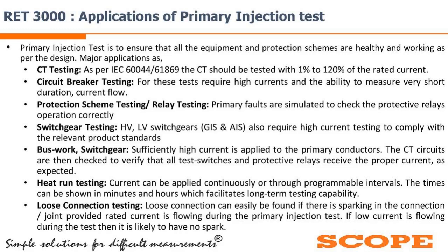Then busbar work or switchgear work. For that also we need to conduct a primary current injection test. Heat run testing is also important. For that we need to apply current continuously at programmable intervals. The times can be shown in minutes and hours, which facilitates long-term testing capability.